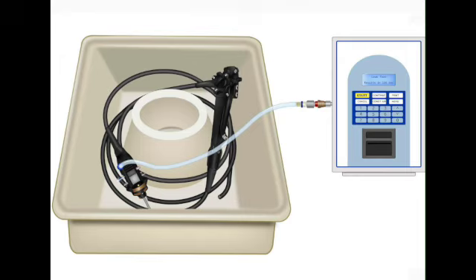That's a great way to think about it. So we'll leave you with this to think about. The lesson here seems to be that a mechanical failure is so often the root of an infectious risk. Now, if these sources focus so much on the vulnerability of seals and O-rings in an endoscope, what other overlooked mechanical failure points might be hiding in plain sight in other complex, life-saving equipment, from ventilators to surgical robots? What requires that same immediate, uncompromising attention before it becomes a risk? Think about the fundamental physical strength of the tools we trust with our lives.